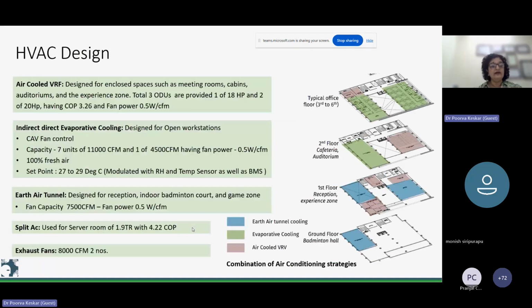The HVAC design here is a mixed mode HVAC system with low energy cooling systems. The ground floor was typically using an earth air tunnel. It was designed for reception, indoor badminton court and game zone. The fan capacity was 7,500 CFM and fan power here was 0.5 watts per CFM. Then for the open offices, we tried to use evaporative cooling. And for the cabins, which had multiple, rather diverse, occupancy, we used the air-cooled VRF.